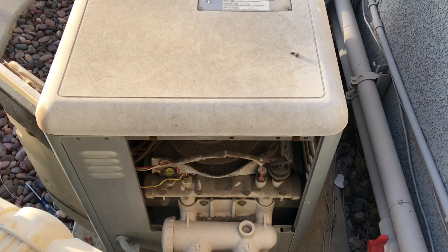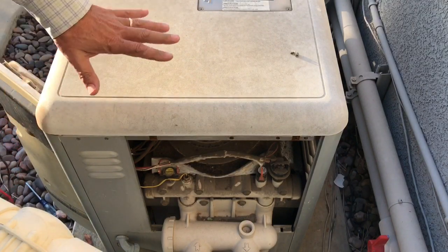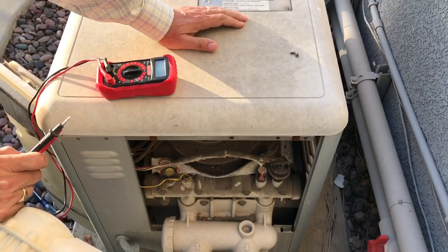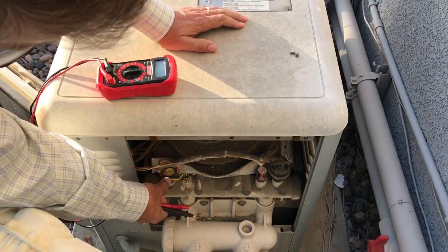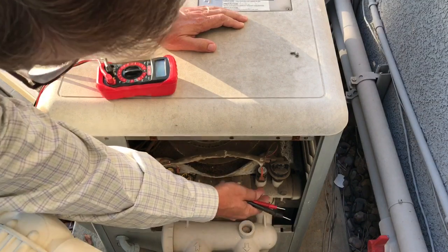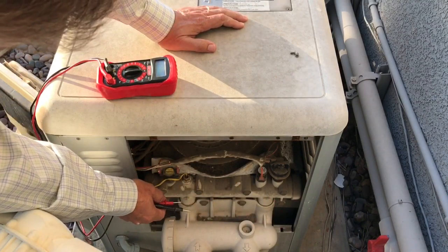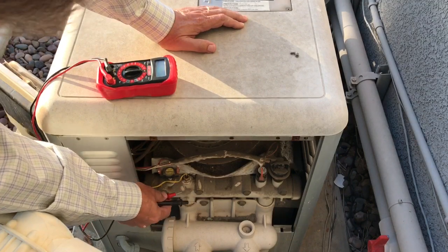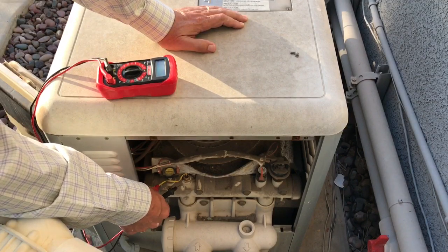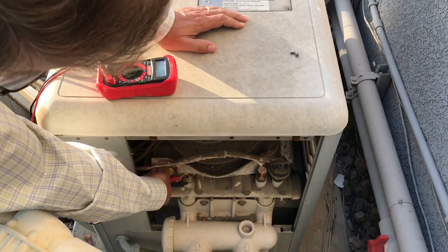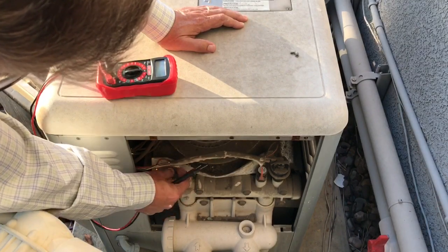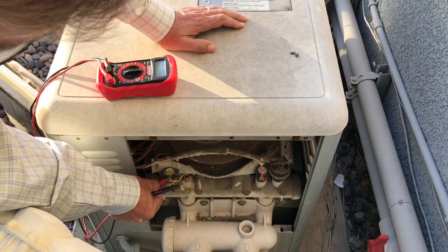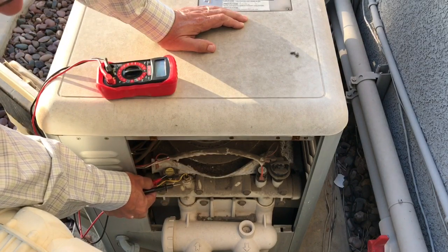Okay, so now with the pump off and the power off, we'll make sure there's no power going to any of the connections. We're going to check these two switches. Like I said, this is the low temperature and the high temperature. These are what they call normally closed switches, meaning that if you were to check continuity, the power from one terminal, like on this side, goes to this terminal, from one side to the other, when the switch is in the normally closed position.